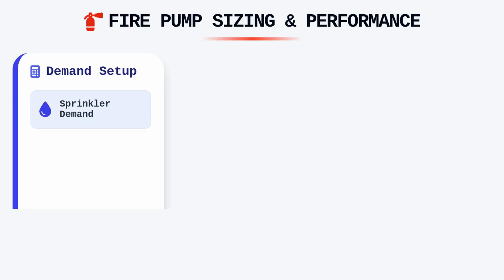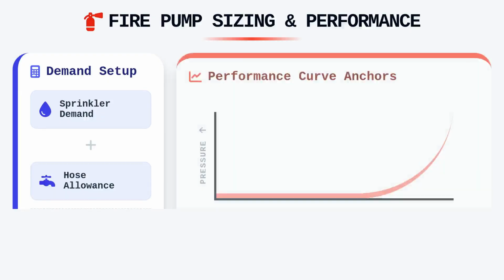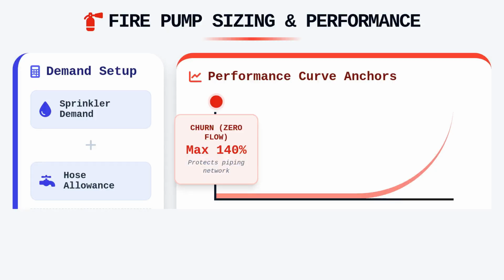When we approach fire pump sizing, we must first establish the required fire demand, which involves summing up the sprinkler system demand plus the required hose stream allowance mandated by the relevant NFPA installation standard. This total flow and pressure requirement dictates the performance characteristics of the pump. A pump is not chosen based on a single point of operation, but rather its ability to traverse a performance curve that starts at churn, which is zero flow, and extends to at least 150% of the rated capacity.